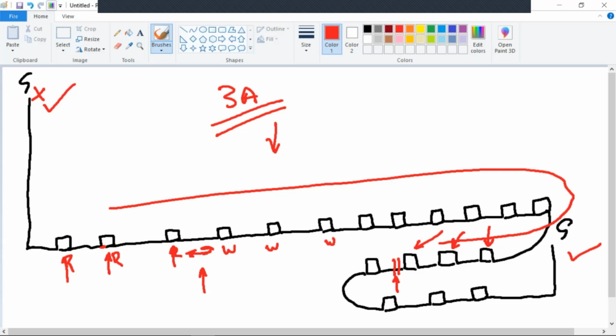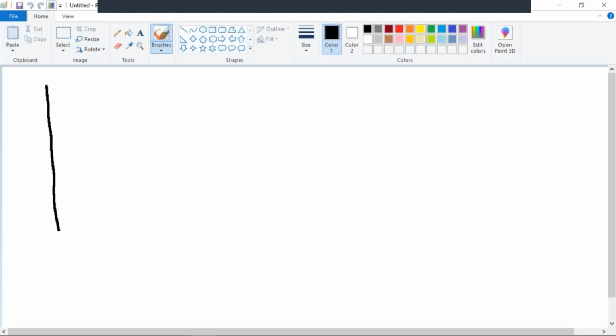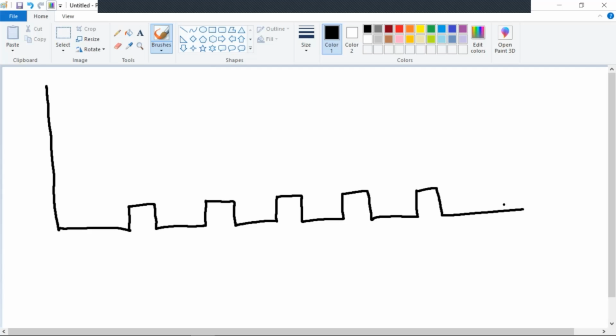Another scenario, and this is what some companies do, Professor V, jump in on this one, is they'll come into a subdivision, dip pole, transformer, and I'm just going to draw 5 for this situation. Transformer, and out. They'll put a fault indicator here at the first one, and they'll skip a transformer. Skip fault indicator here. So if I have a red indication here, I skip this transformer, and I've got a white indicator here. It does isolate my area into this span, this transformer, and this span to here.